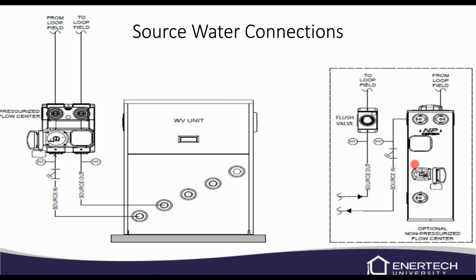On the non-pressurized flow center, we're not going to flush through the flow center. So you will need to add a field installed, insulated flush block. You can make your own, you can purchase one from us. Doesn't really matter to me. Just make sure that you're installing your strainer in your source in water line as well. But that's a requirement. They come with the unit. So when we send them with the unit, it's not just a, hey, I'm not going to use it. It's, hey, you have to use it.